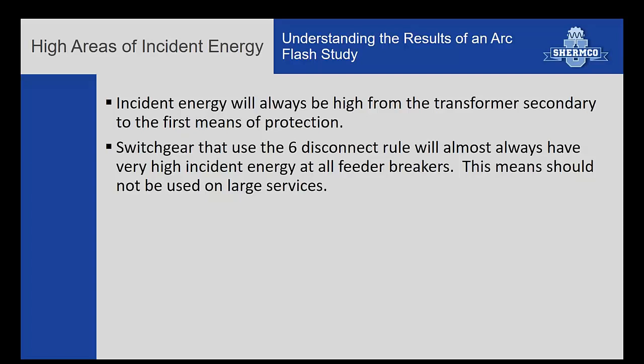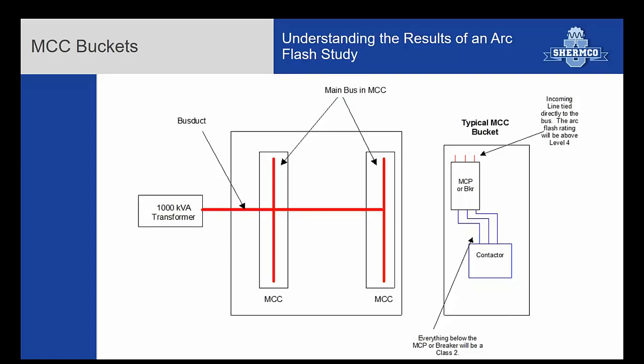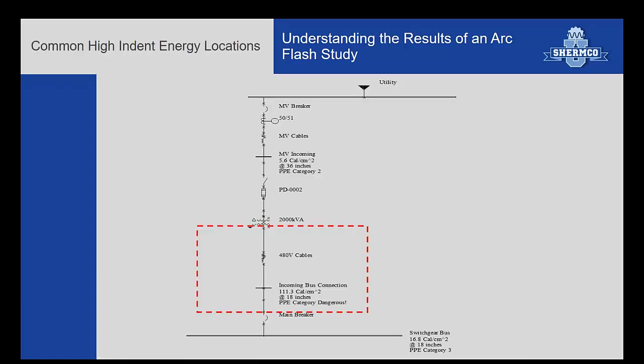So with that, let me go back 1 second. In these cases, and even in the previous case on the transformer, sometimes just writing procedures, you might not ever rack the main breaker off the bus that's dangerous. Or that might be the only task that you want to do. Here, if you're trying to rack this breaker off the bus, and it's single-ended, you might not ever really need to rack this breaker while it is energized.